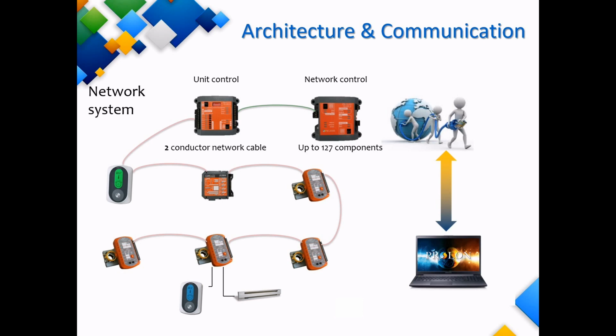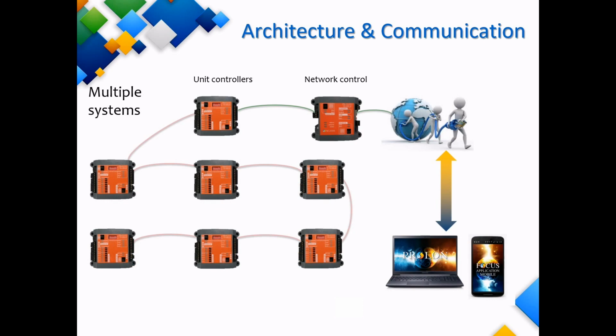Now, it's not about having one rooftop with 100 zones. No, we could set up 10 rooftops, and each of those units could have 10 zones. That would be 10 rooftops and 100 zones, which brings our total up to 110 devices. We'd still have room for another 17 controllers on that network. There is no limit on the types of controllers on any given network. So you can mix and match all our different controllers as long as we are within the 127 device limit.